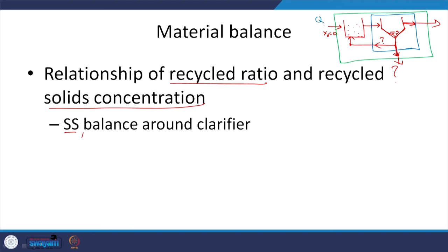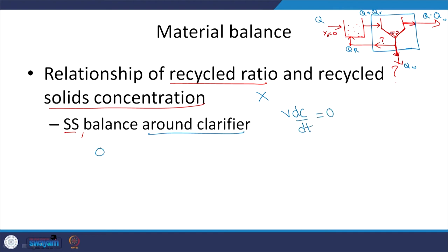The flow coming in is Q, the effluent is Q minus Q_w, and the waste sludge is Q_w. The recycle flow is Q_r. So the flow entering the clarifier is Q plus Q_r. We apply the mass balance on x around the clarifier. At steady state, V dc/dt equals zero. Microorganisms enter via (Q plus Q_r) times x. They leave via three routes: (Q minus Q_w) times x_effluent, Q_w times x_r in the waste sludge, and Q_r times x_r in the recycle stream.